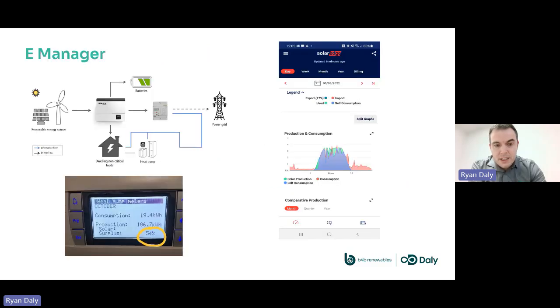Energy management. So the particular system we do, if there's PV on the roof or a wind turbine, we fit a little meter on the incoming power supply. That's just giving information to the heat pump as to what potentially is being exported back to the grid. So in our particular scenario with this setup, if we have more than 0.5 kilowatt in domestic going back to the grid over a period of 5 minutes, we can trigger our heat pump to come on and start using that electricity that's been generated for free on the roof.